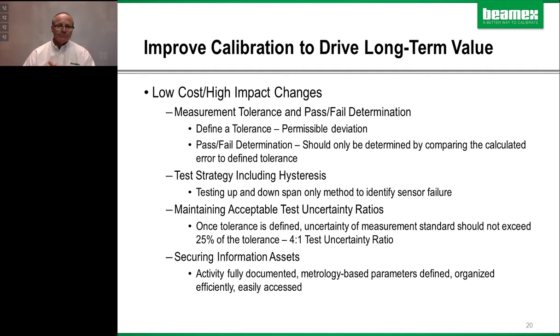Pass-fail determination is actually calculating using that tolerance. Are we within tolerance or not? That should only be done by calculating the error based on the tolerance. In the survey, a lot of errors are based on a percent of span. It can be a percent of reading. It can be an engineering unit, such as a milliamp. But it requires some math out in the process for that technician to determine if we're within a pass-fail status.